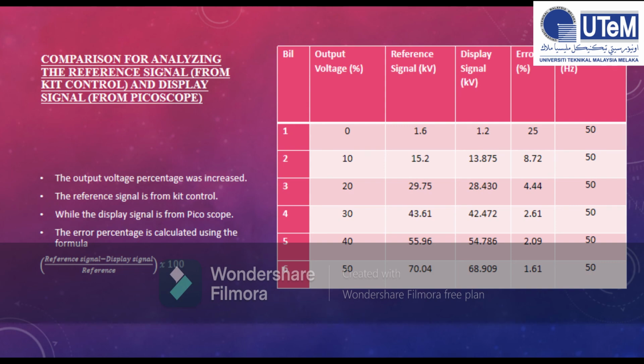Comparison for analyzing the reference signal and display signal. The output voltage percentage was increased by 10% consecutively starting from 0% up until 50%. The reference signal from the kit control and the display signal from picoscope is recorded. The percentage of error is then calculated using the formula. The frequency remains same, which is 50 Hz throughout the experiment.